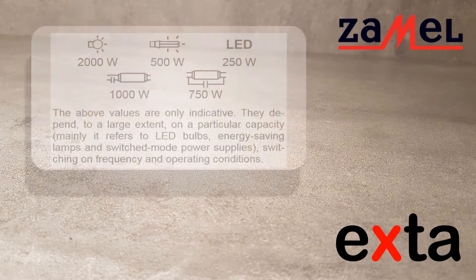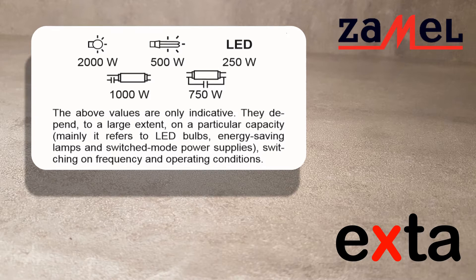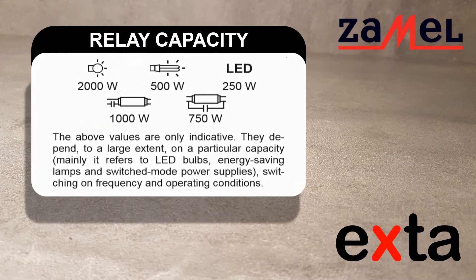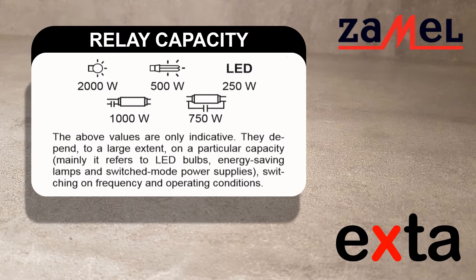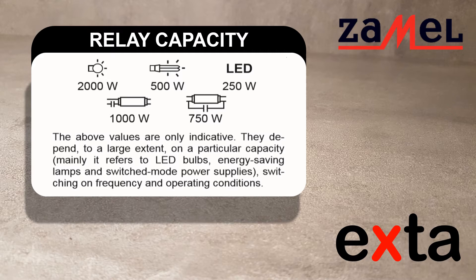The maximum load capacity of relay outputs PBM-07 must not exceed 2000 Watt in the case of incandescent sources, 500 Watt for energy saving sources, 250 Watt for LED lighting, and respectively 1000 or 750 Watt for fluorescent tubes with the appropriate ignition system.